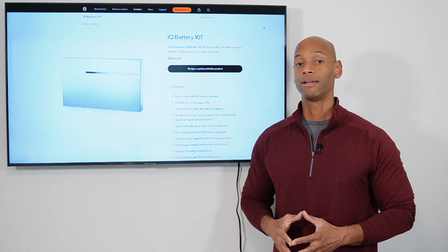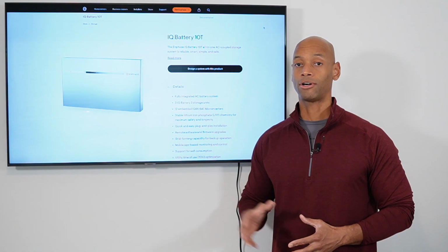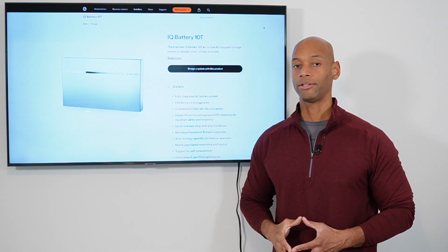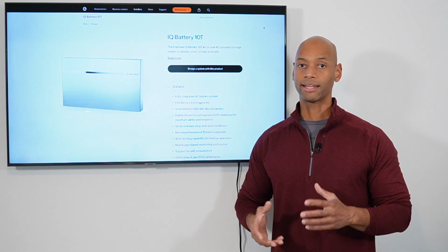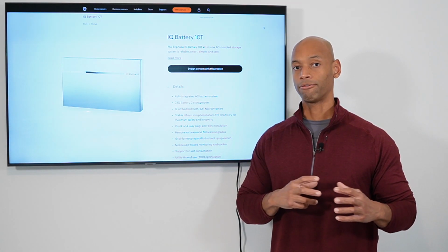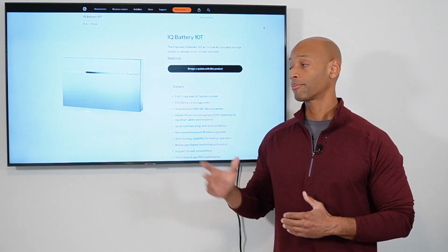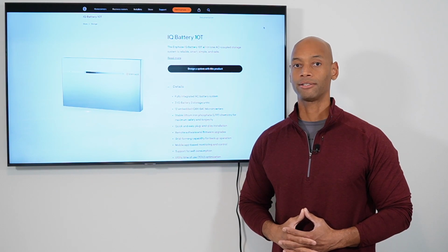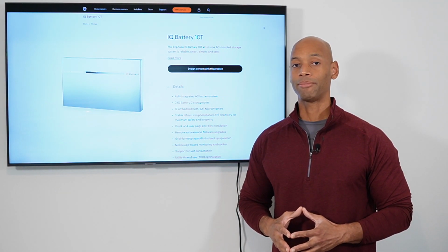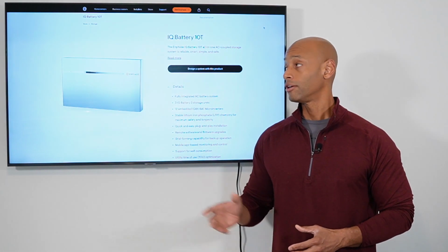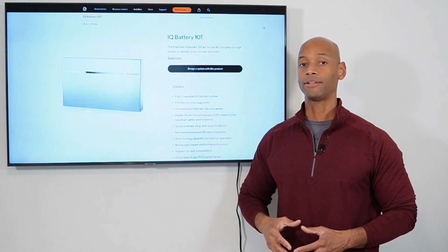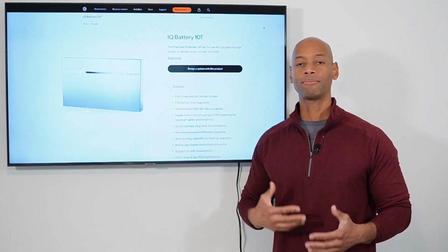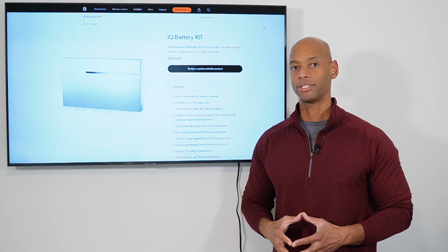However, what I can tell you is that our installation partners are very reluctant to offer the current generation battery with anything other than the current generation IQ8 microinverters. And I think a lot of that has to do with the compatibility and the firmware on the microinverters being able to talk properly to the battery so that everything works together seamlessly as one integrated system. I should also comment that on the projects we've done using the Enphase battery, whether it's the older Encharge 10 or the new IQ Battery 10, all of the installations seem to require some sort of a firmware update at the time of system commissioning.